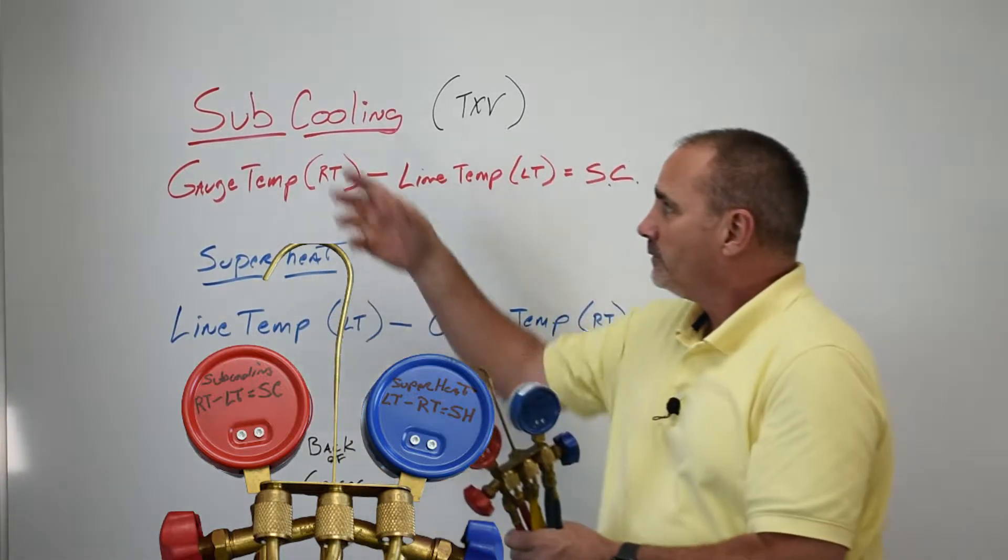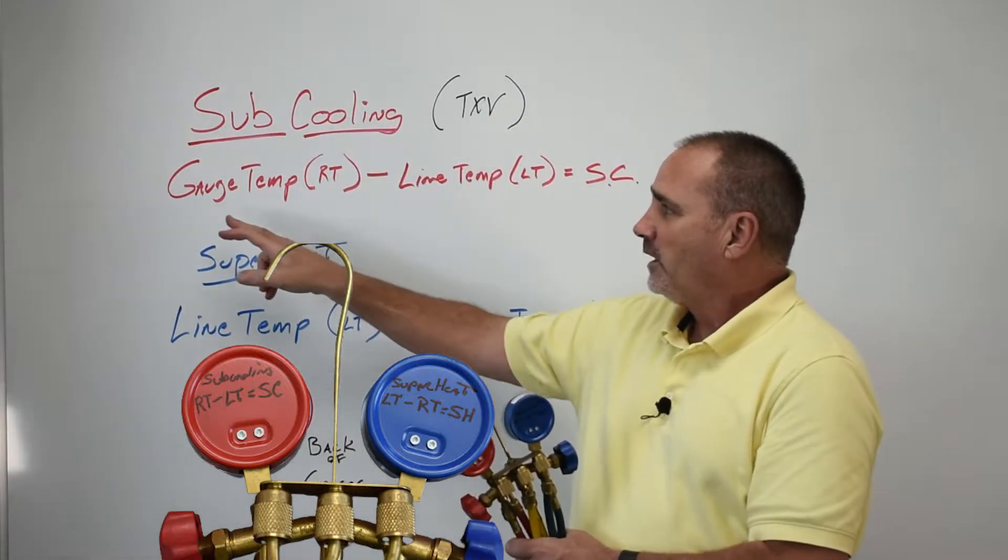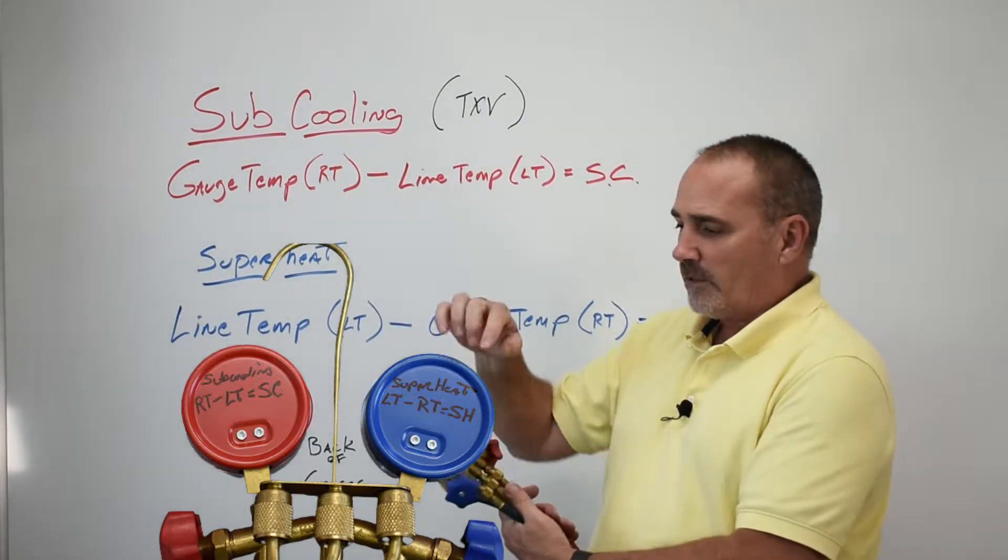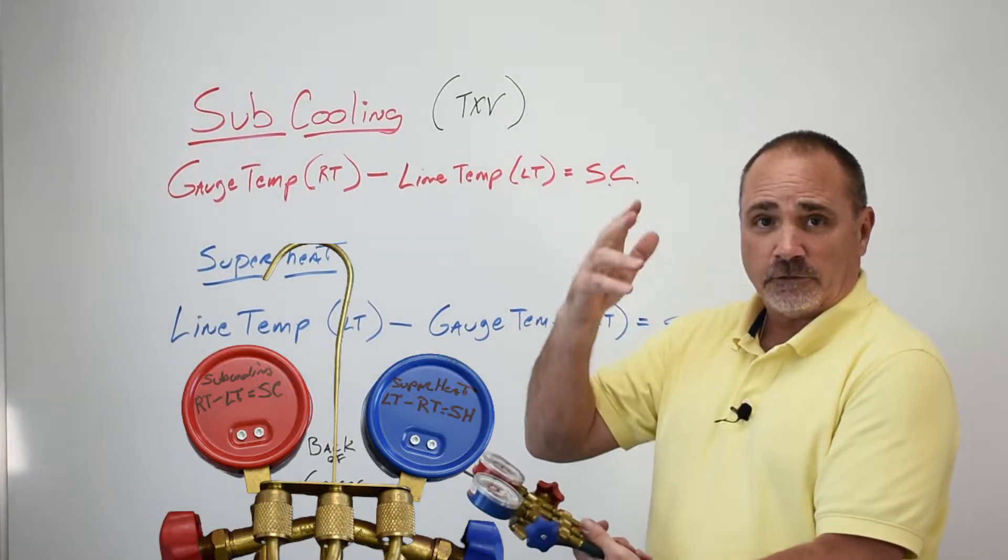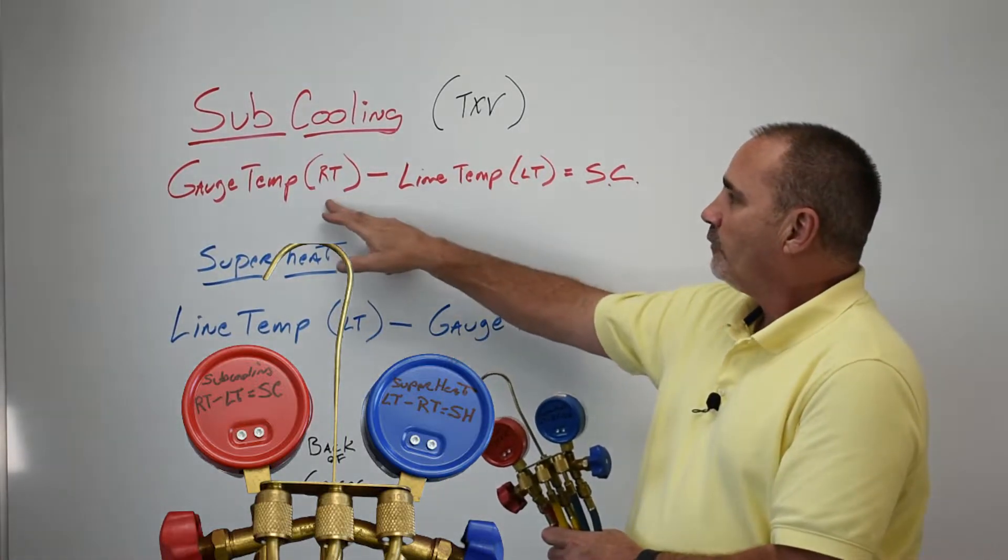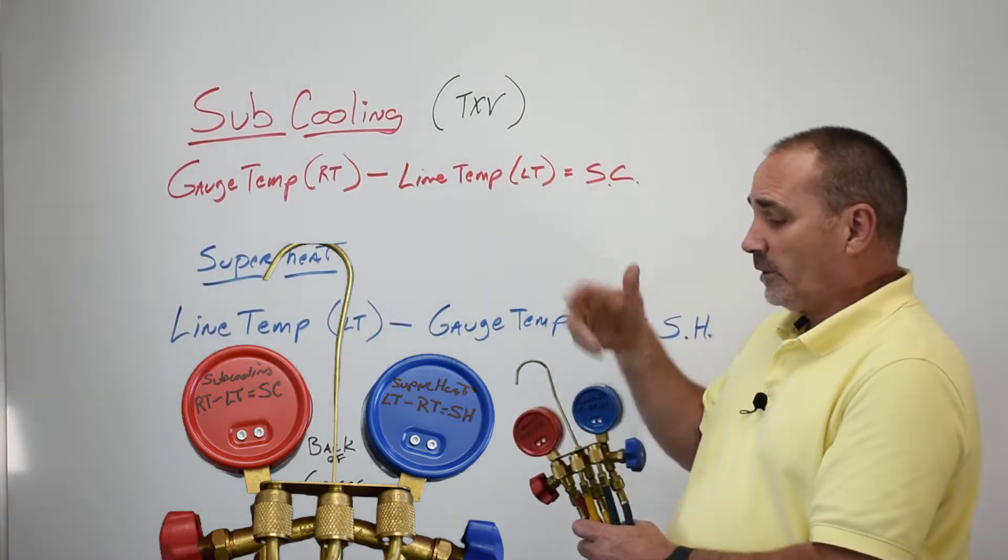What I suggested - and this is the gauges of a young kid - we just wrote on the back: sub-cooling, typically for TXV, gauge temp (of course I wrote it as RT for refrigeration temp), so whatever refrigerant you're looking at, be it R-22 or 410A or whatever, refrigeration temp on the gauge minus the line temp equals your sub-cooling. Easy to remember, it's right there.